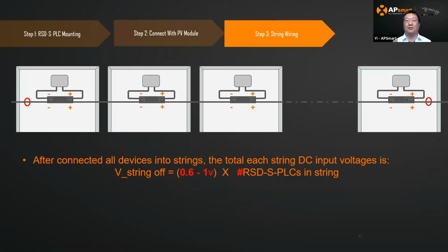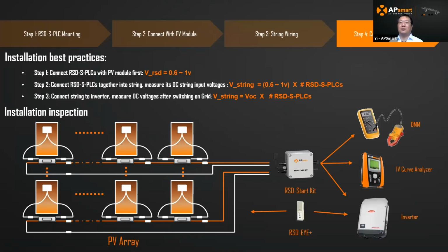Yeah, so when you install that into a string, what's the open circuit voltage? That's the very important number you need to look at next after you install the string. Basically, you just use the 0.6 up to 1 volt times how many devices you have in the string. For instance, if you install 10 modules in one string, you should be able to see between 6 volt up to 10 volt, in that range. As long as you're within that range, you're okay. Next, please.